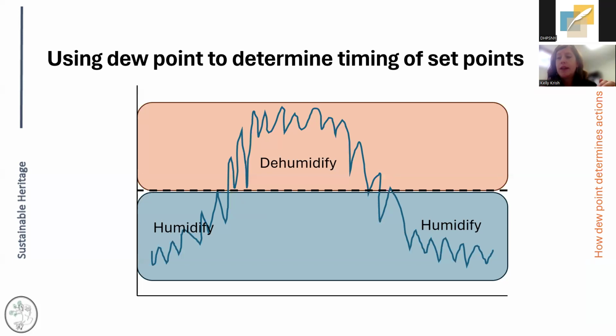It can also be useful in determining the timing of the set points. For example, down here, we're getting ready to change over to our summer set points. We have different conditions for different times of the year. If we don't change over to our summer conditions and we stay at our cooler temperatures, that small bucket is going to fill with all of our added summer moisture very quickly, and we're going to have issues with high relative humidity. So we need to transition to a bigger bucket to hold that higher level of moisture. The easiest way to tell when to change from your winter set points to your summer set points, again, is to look at that outside air dew point graph. You'll often see a time of year when it's consistently crossing the line that you've set with your set point. And once it's gone beyond that point, you're going to want to switch to the appropriate operation. So once it's consistently above that line, I want to move into dehumidification operations so that I can get it back down. And once it's dropped below that line, I want to switch to humidification so I can raise it up.